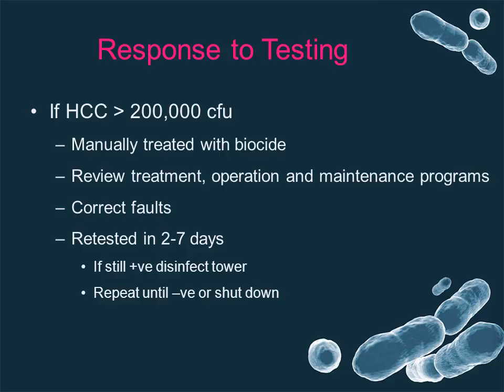If the HCC test returns a result of greater than 200,000 colony-forming units of bacteria, then the owner of the tower must manually treat the tower with additional biocide and review the treatment operation and maintenance programs so that any faults can be corrected. The water must be retested in 2 to 7 days, and if it still remains positive, then the tower must be disinfected, and this process repeated until an appropriate result is received or the tower is shut down.